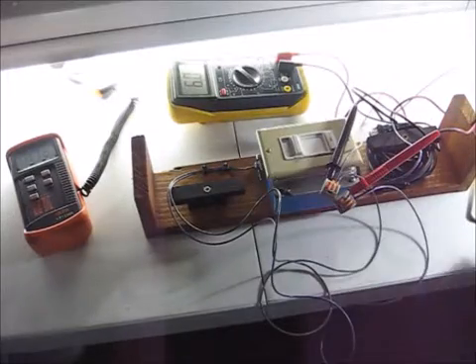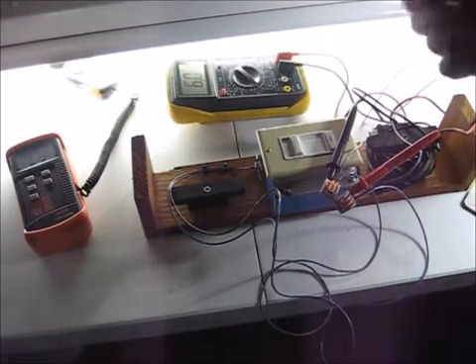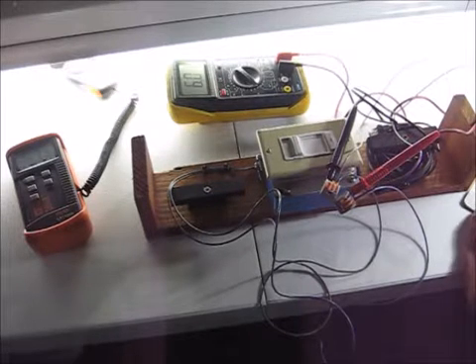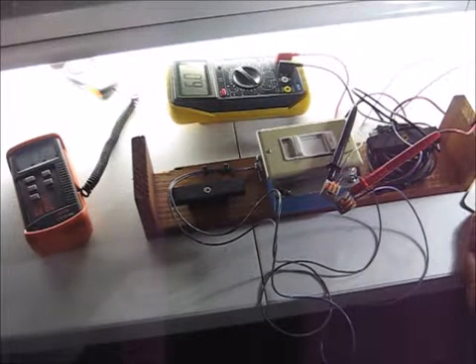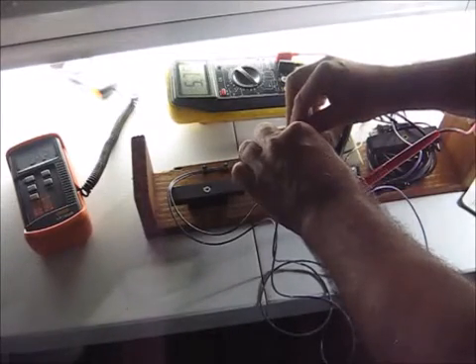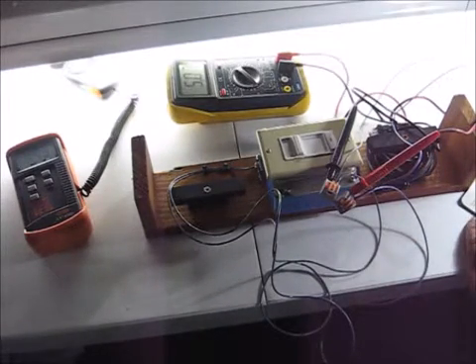I'm going to bring it down to 6. Now, if you're doing this on site, you may not even know what's inside the 0 to 10 volt luminaires, but this is characterizing them. I've got 173-ish at 6 volts. At 5, we've got about 148.